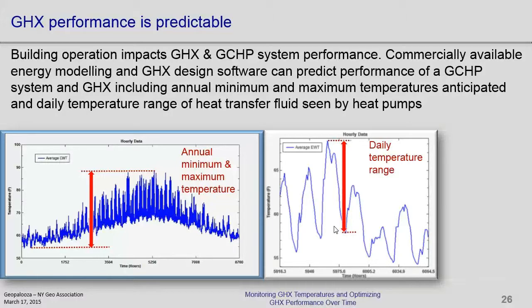We're using the horizontal portion to dissipate excess heat in the winter because it's very shallow, or it can absorb a lot of solar heat in the summertime when the ground is a bit warmer and dump that into the ground loop. They've developed software that can see if the system is off target today and what the implications are going to be in two, three or four months, and try to get it back on target. I haven't seen any systems yet, but they're talking about being able to plug into a weather station. If you can see there's potentially a big heat wave coming over the next couple of weeks, you can pre-cool that ground heat exchanger ahead of time, and it'll give it more room to absorb heat during that time period.